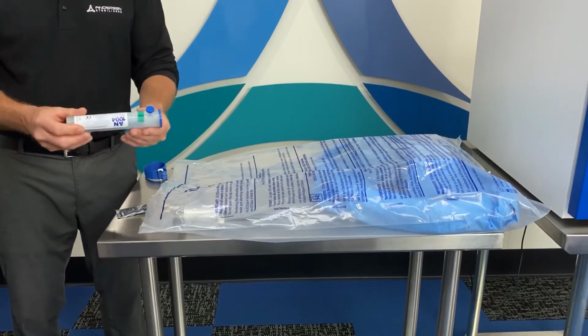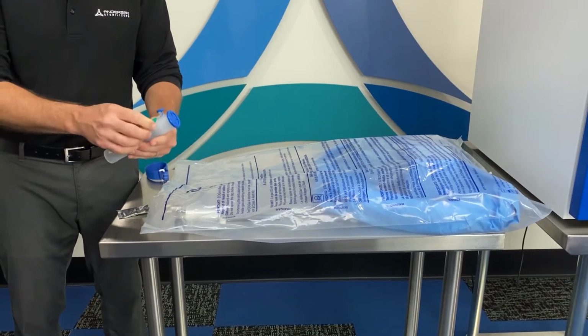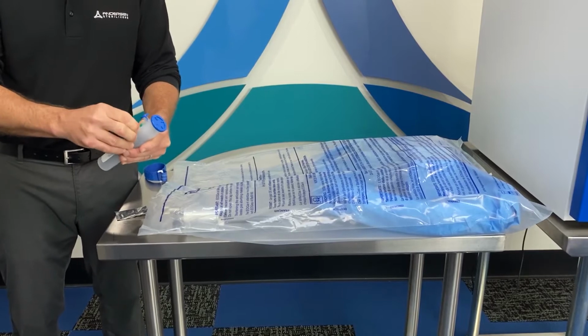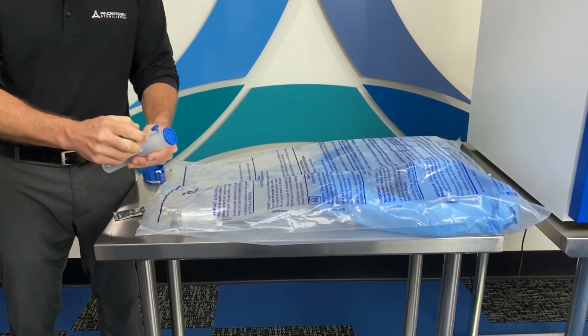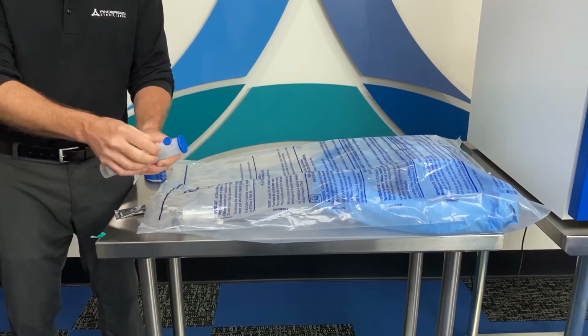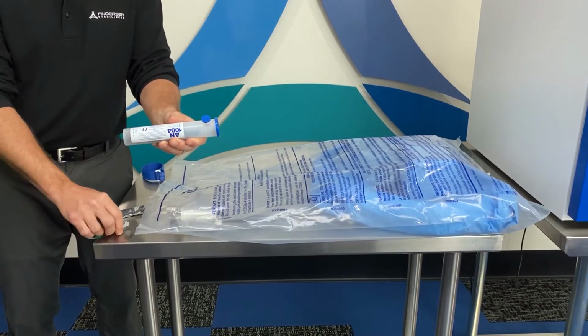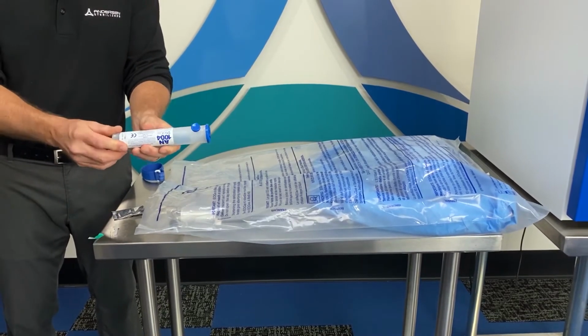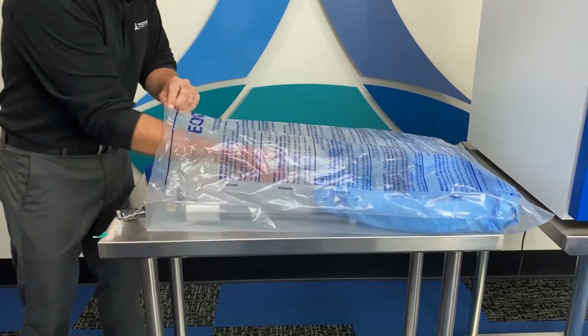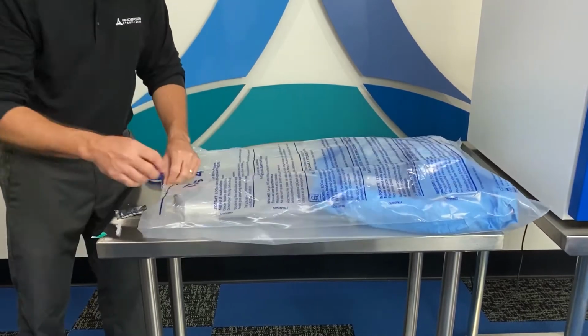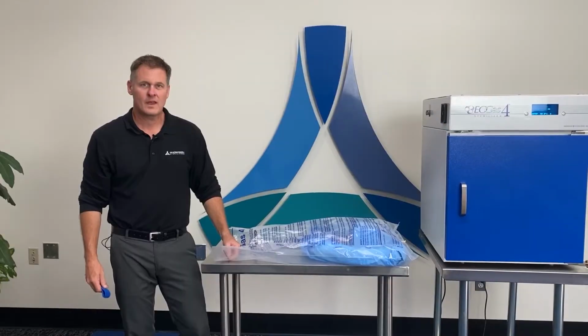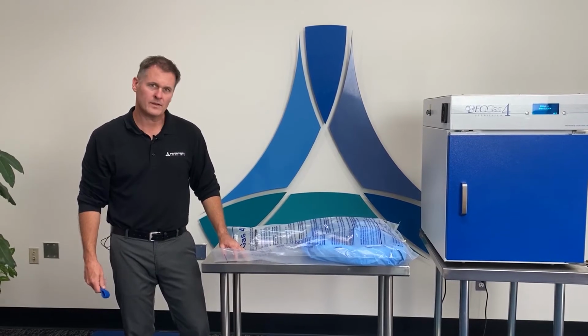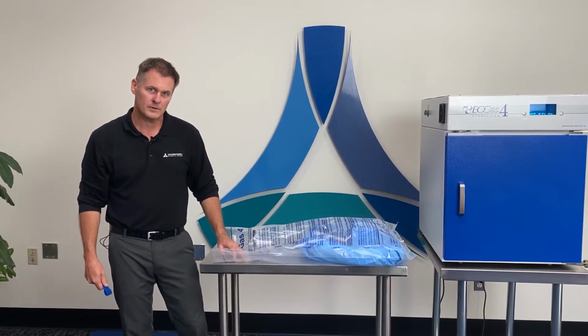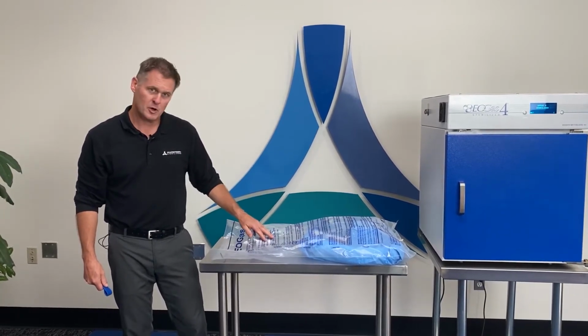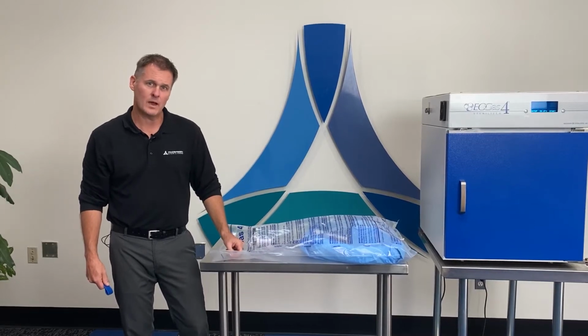And finally, you'll take your gas cartridge, remove the tape, and trigger guard. Place those aside. Place the cartridge on top of your items in the sterilization liner bag. At this point, we've loaded our bag with the items we're going to sterilize and all the consumables. We've prepped the purge probe, and now we need to seal the bag around the purge probe.